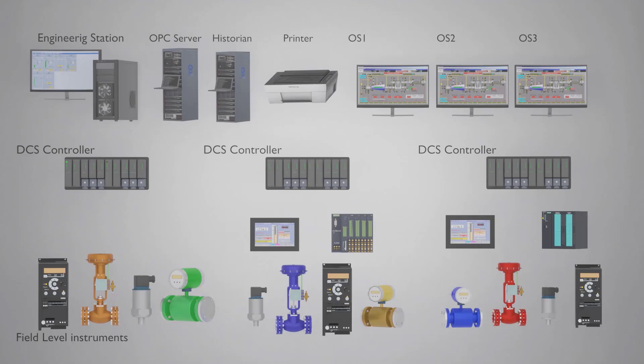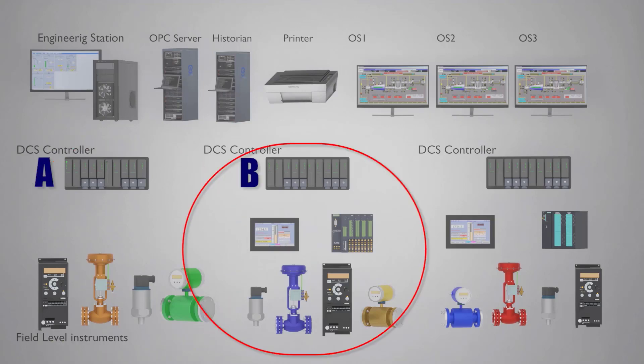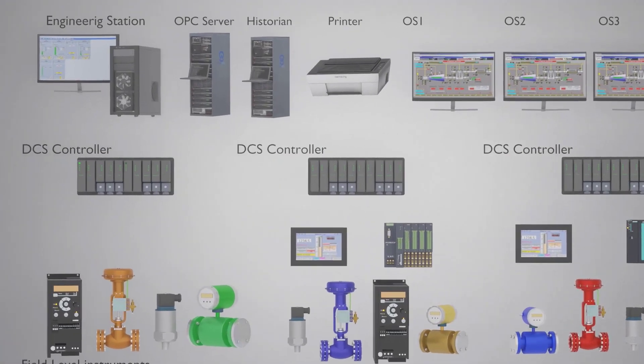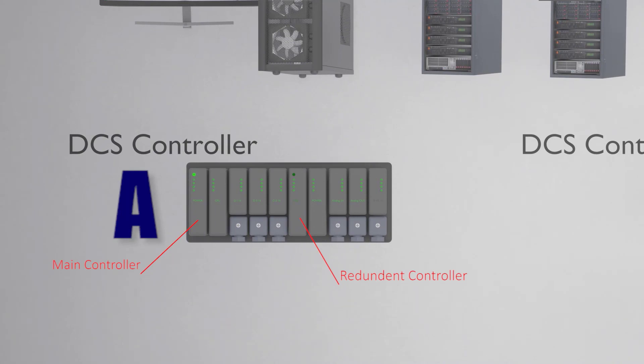In a DCS architecture, you would have a unique controller or control station for each area — let's say area A, area B, and area C. For area A, you have one control station. In that control station, you have two controllers: one is the main controller and one is the redundant one. In the case of failure of the main controller, the redundant controller will take over. So in each area in a DCS network, you have one main controller and one acting as redundant.